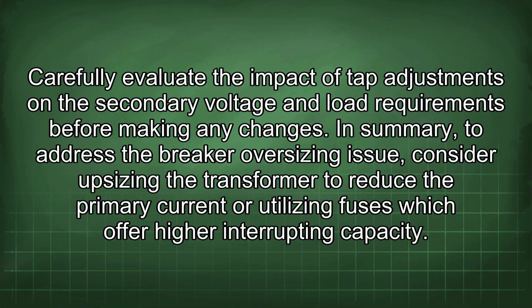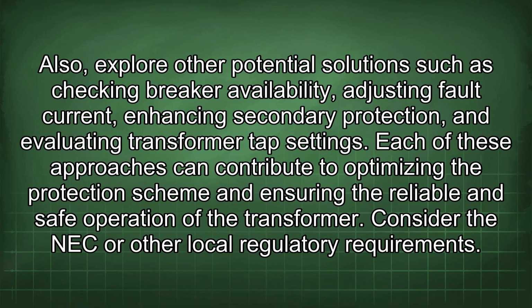In summary, to address the breaker oversizing issue, consider upsizing the transformer to reduce the primary current or utilizing fuses, which offer higher interrupting capacity. Also, explore other potential solutions such as checking breaker availability, adjusting fault current, enhancing secondary protection, and evaluating transformer tap settings. Each of these approaches can contribute to optimizing the protection scheme and ensuring the reliable and safe operation of the transformer. Consider the NEC or other local regulatory requirements.